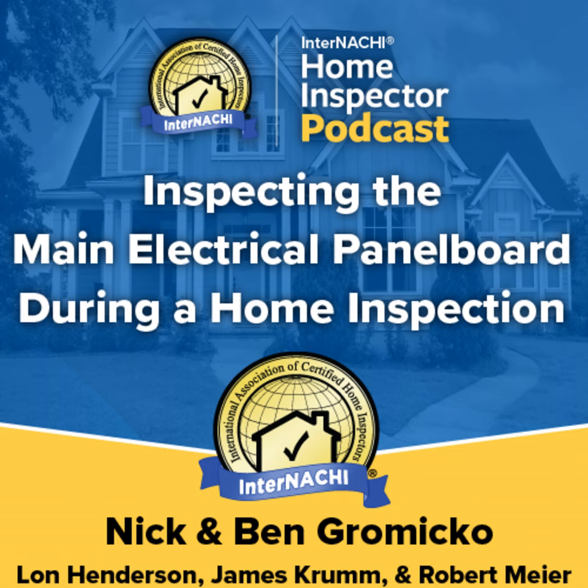Complete panel board replacement with the most modern equipment remains the best recommendation. Note that in most areas, replacement panel boards are not required to meet all of the latest code requirements. If there is a need to modify or extend the old breaker panel to include modern AFCI breakers, the old panel boards may not be able to accommodate them. A home inspector should know what the local community or state requires.